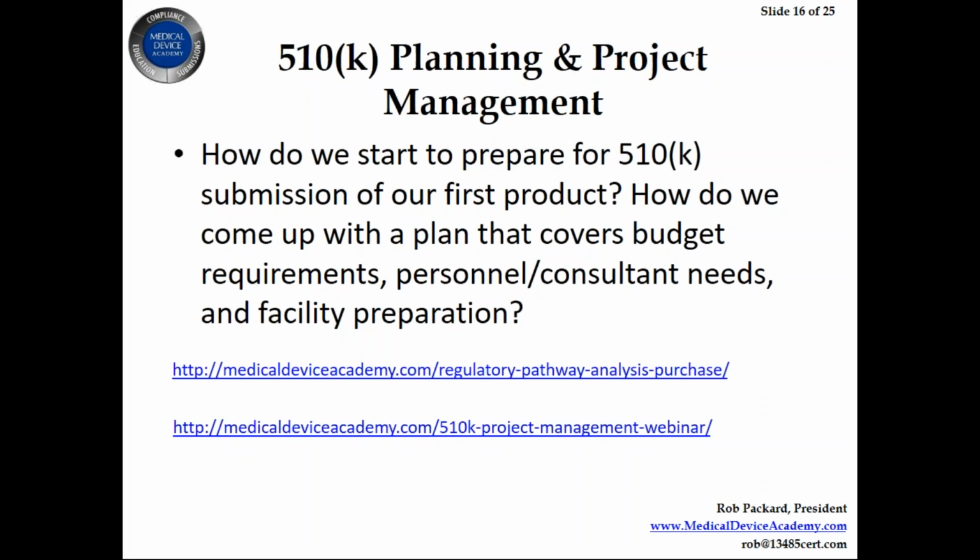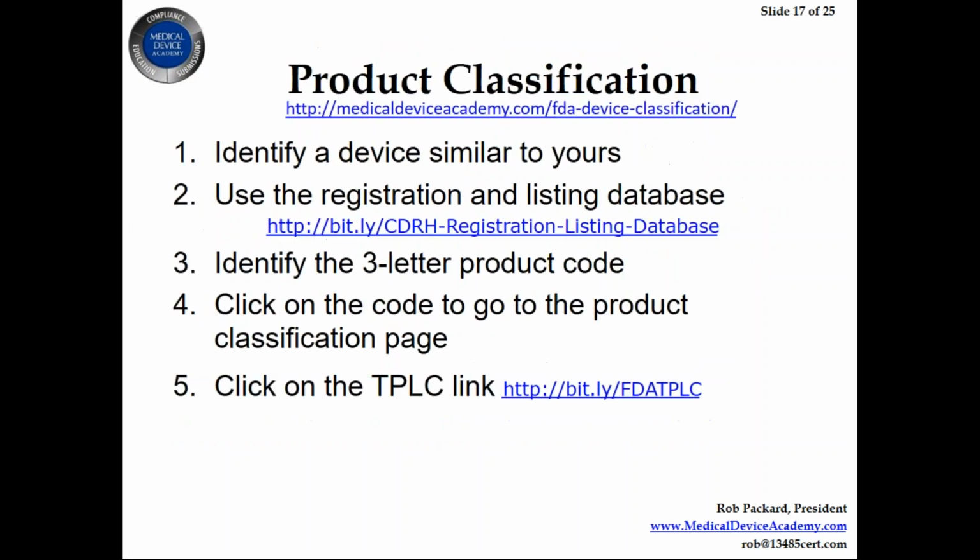So I try to have all the testing done, and I want to submit the day that the last test is done, so I make sure that all the documents supporting that are written in parallel with the testing, and I fill in the blanks as I get the test results. So I pursue the two activities in parallel, and at the very end of the project, when the last test report comes in, then we actually submit a 510K.